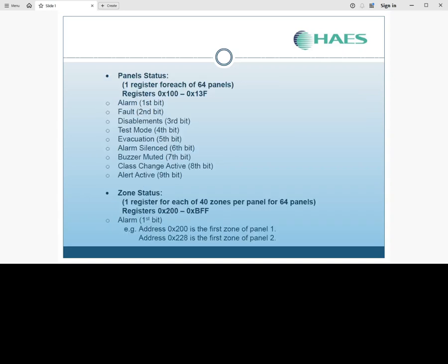Panel status. 1 register for each of the 64 panels. Registers 0x100 to 0x13F. The alarm will be the first bit. Fault is the second bit. Disablement's third bit. Test mode fourth bit. Evacuation is the fifth bit. Alarm silenced will be the sixth bit. Buzzer muted, seventh bit. Class change active is the eighth bit. And the alert active is the ninth bit.